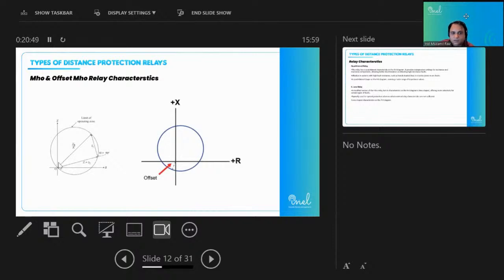So to avoid this issue, there is another characteristic, which is the offset Mho. Now it is a bit offset from this origin, and due to this portion of the curve, this characteristic, if the fault occurs at this bus bar location, then this relay can be sure about the location and will consider it an in-zone fault, protect that equipment from the fault, and operate as soon as we have set its time. So this is offset Mho, this is Mho. There is a little bit of difference between these two, and hopefully you got my point. Like, what are the benefits of the Mho relay and what are the benefits of the offset Mho relay.